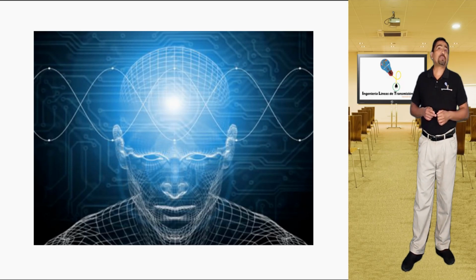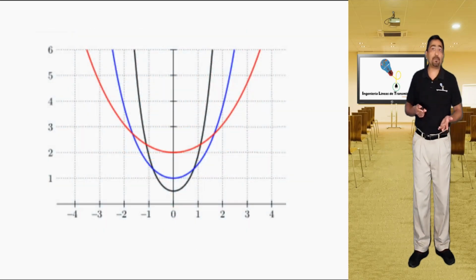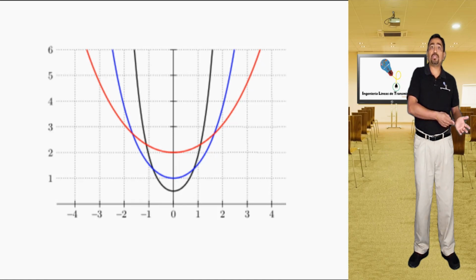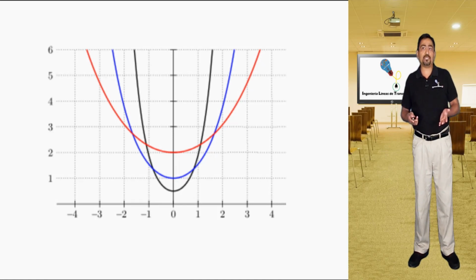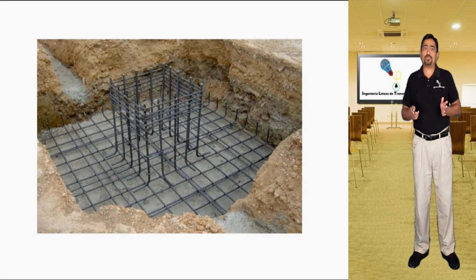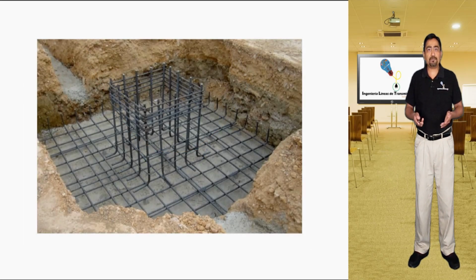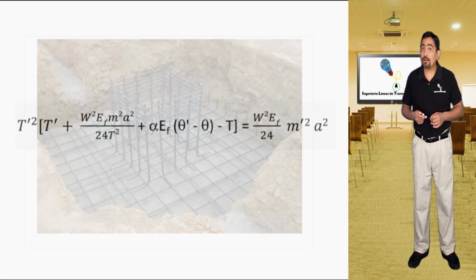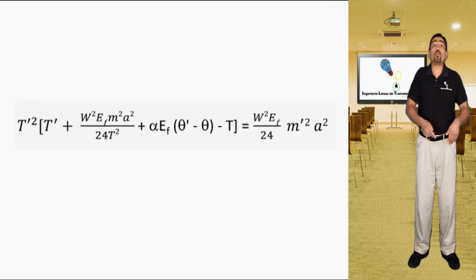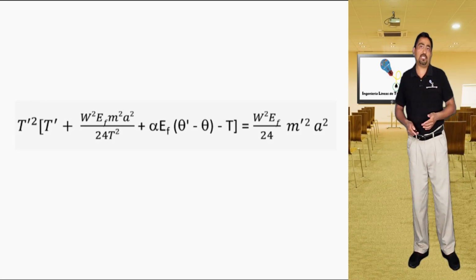In the case of transmission lines, I've seen how the mechanical calculation of a parabola or catenary is required prior to the structure's locations engineering. This calculation is the basis for the design of any transmission line, and because of this, it is necessary to know the concepts of the change of state equation, how it works and what it really represents physically.